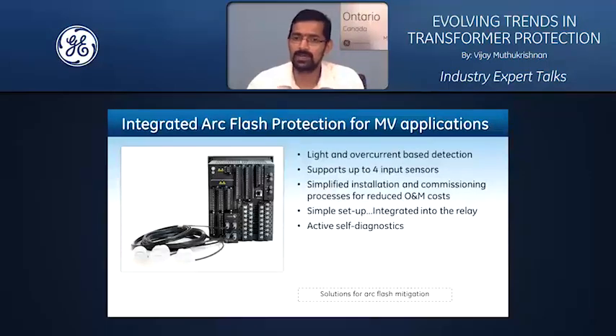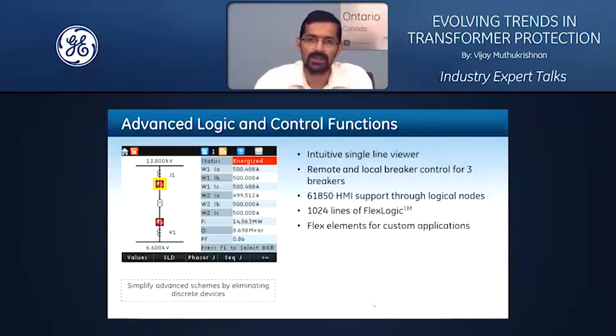So this type of integrated arc flash protection allows you to build a simplified arc flash solution. Having covered the variety of application needs on the protection side, let's focus a little bit on the advanced logic and control functionality. We have a relay. If that relay is able to give you a very good visualization, like the 845 with a single line diagram and an intuitive summary of information that you would look for in terms of operational characteristics and parameters of the transformer, that will be very useful from a maintenance and operational perspective.